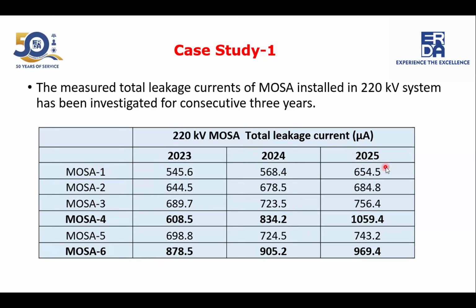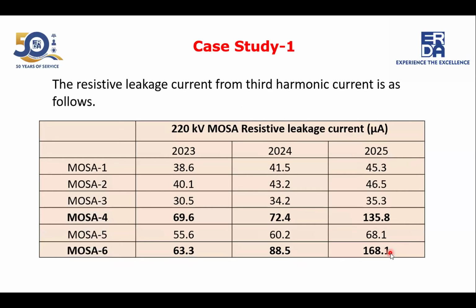If we see the trend analysis, the first year it was 545 microampere, then 568, and then it increased to 654 and so on. The only thing we need to see here is the surge arrestor number MOSA 4 and MOSA 6. These are the results where a little bit of abnormality is there. The initial measurement was somewhere around 600, 608 microampere. Then this year, after 2 years, it increased to 1059.4 microampere. Similarly, for the sixth surge arrestor, the initial measurement was 878.5, and this year, after 2 years, it increased to 969.4. So these trends have increased very much.